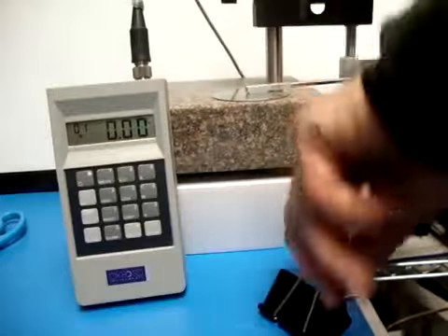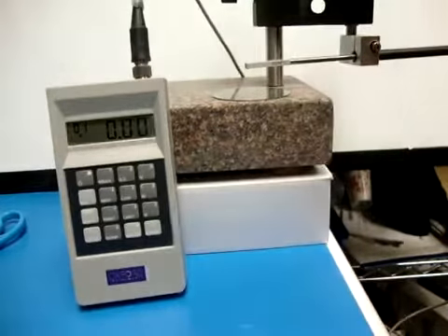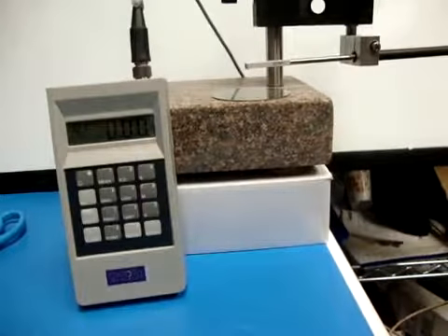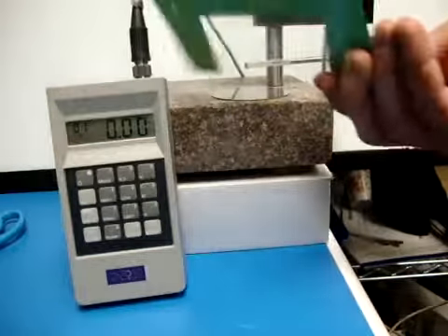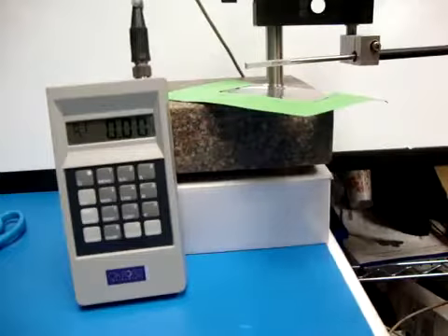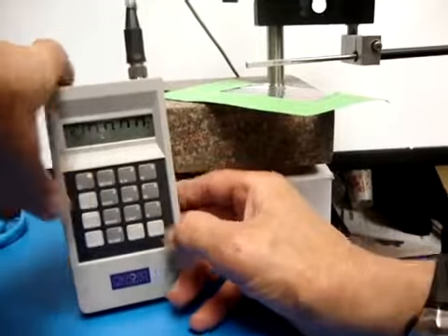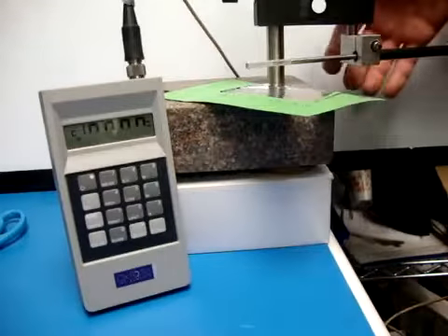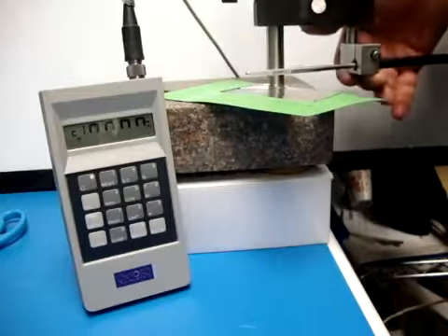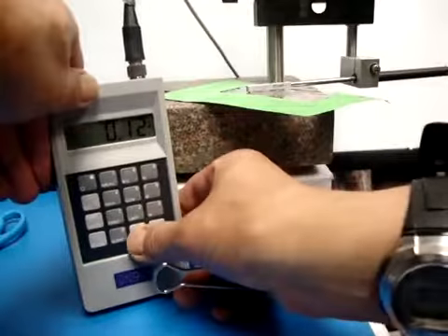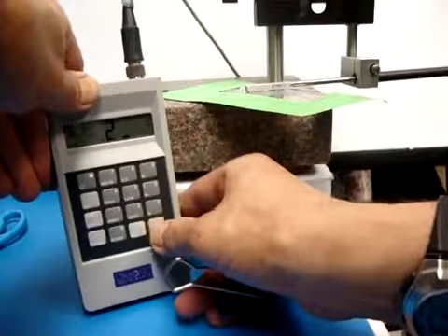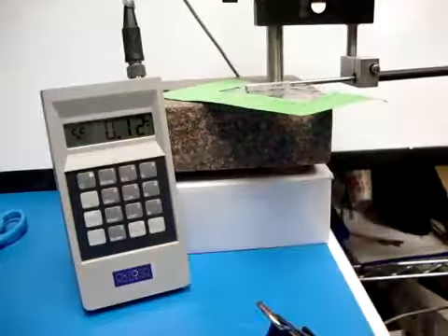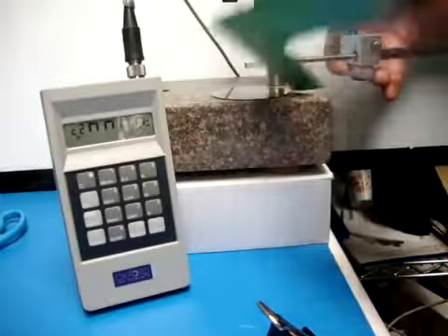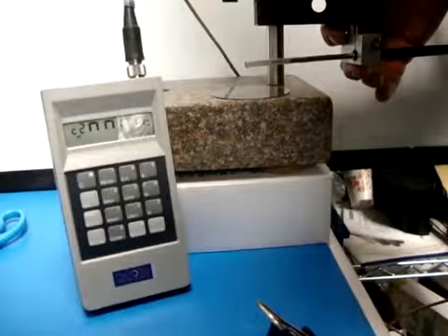So now the next thing to do is pull the probe back up and put on my first shim, which in this case will be 0.2 mils. So I'm going to do a star cal to calibrate it to the shims. Right now it's asking me for the first shim. C1, I would have said S1, but the designers put in C1. So now we drop it down on that shim and enter the value. 0.2. Enter. And now, it's looking for the second shim, so that isn't the value it's reading of the first shim anymore. It's waiting for you to put on a second shim and enter the value.